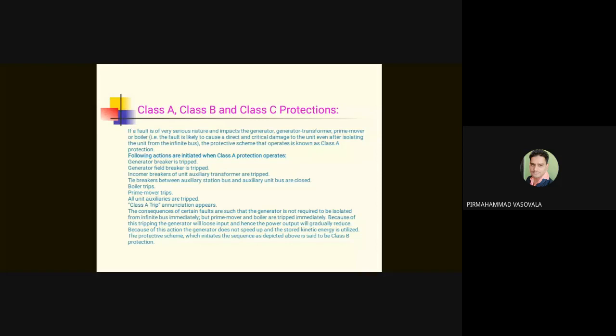If the boiler comes to rest, if the boiler comes to room temperature, then it takes 7 hours to rebuild the boiler to its normal temperature, because the boiler temperature near the furnace is of the order of some 1100 degrees centigrade. Therefore, bringing back the boiler to normal condition takes a very long time and quite a lot of revenue will be lost. Therefore, if class A trips, it's a very big event. But if the damage is going to be very bad, then class A is a must.